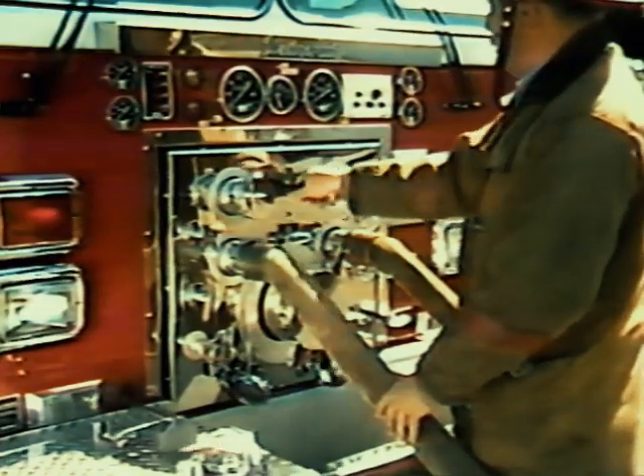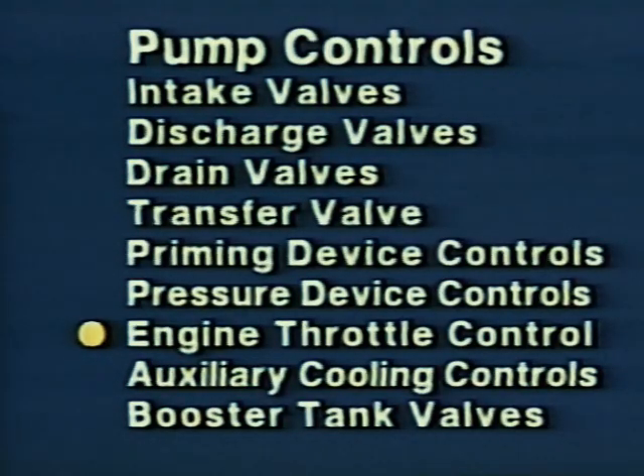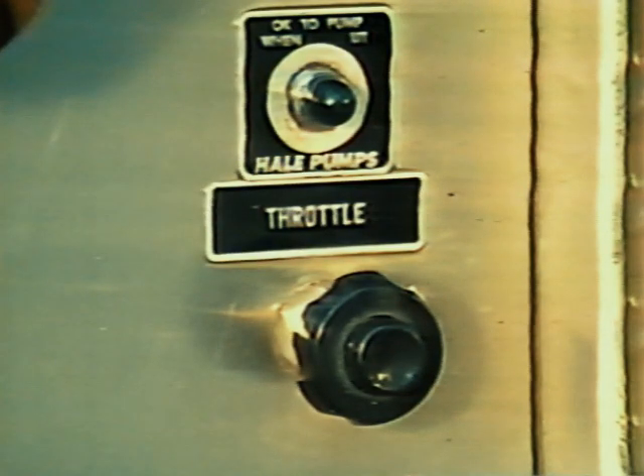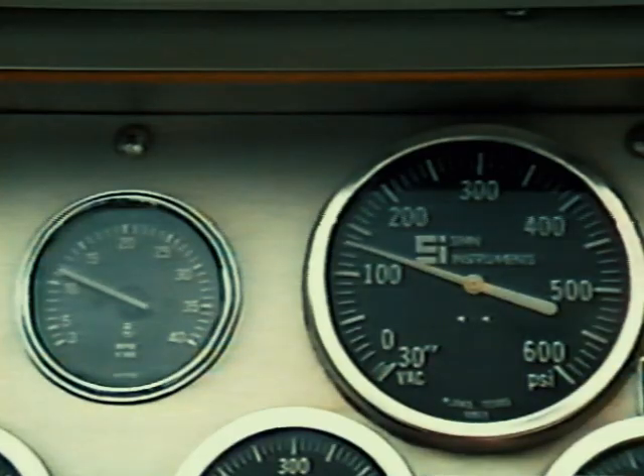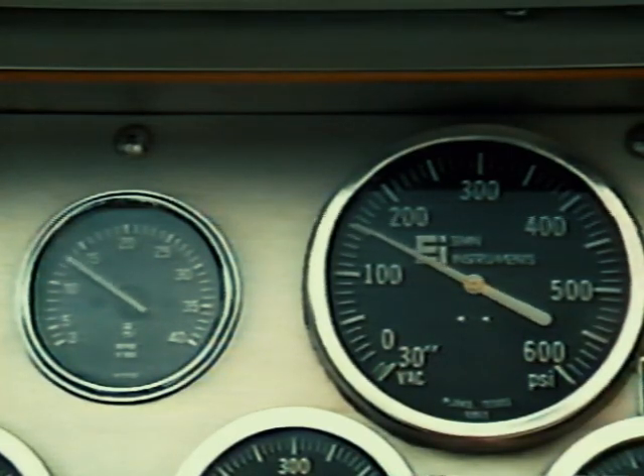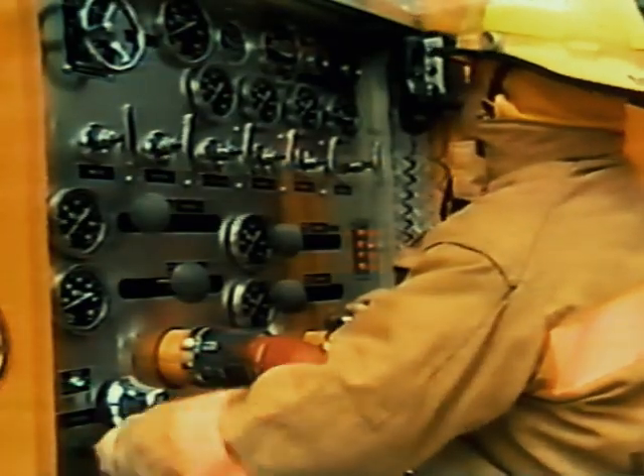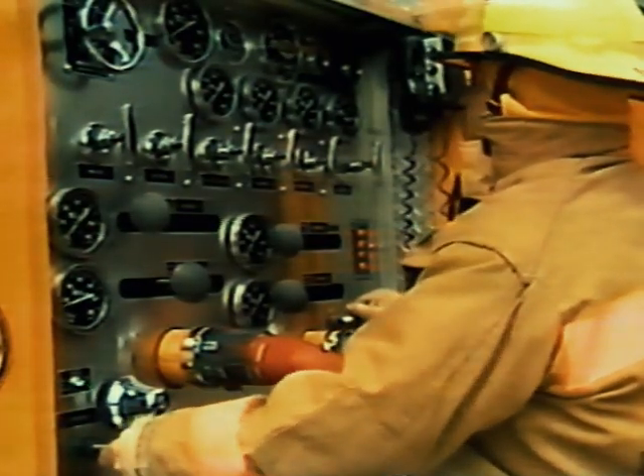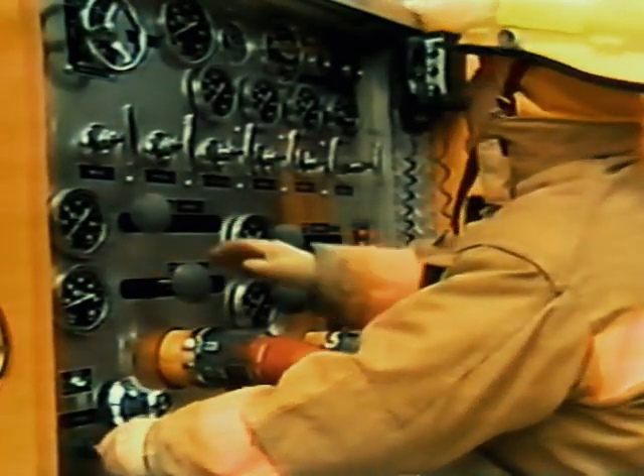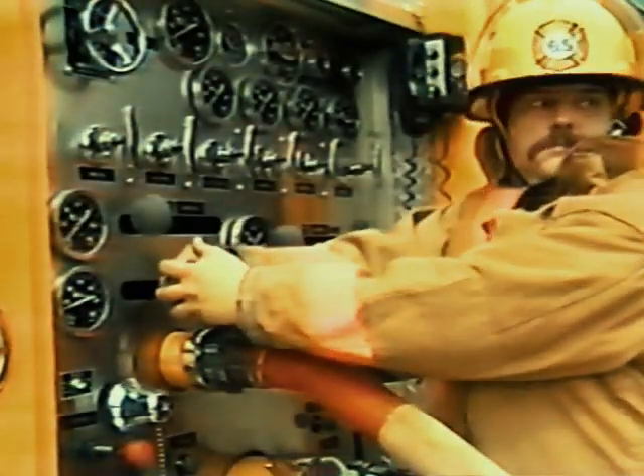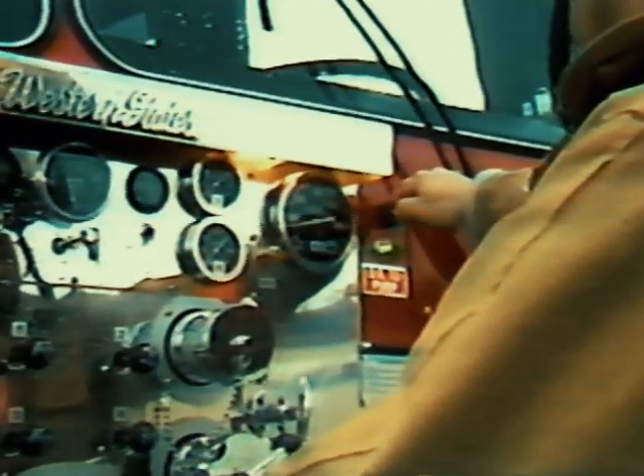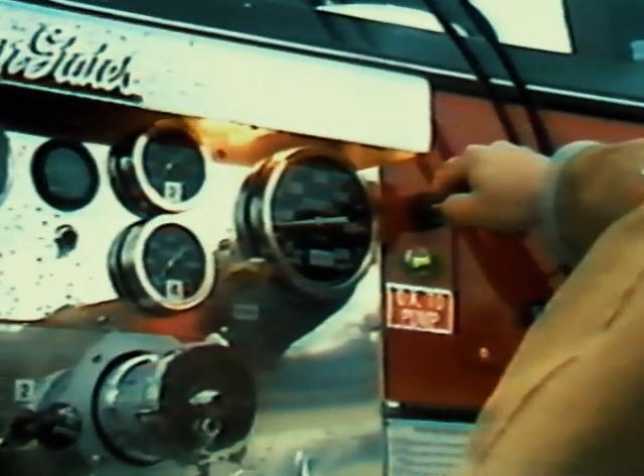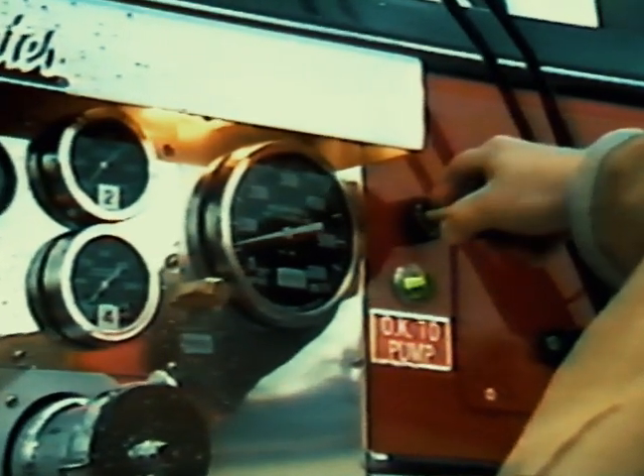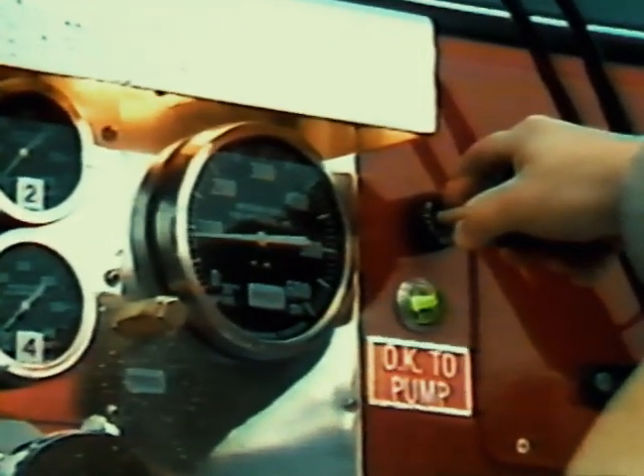The throttle control is a remote throttle that allows the speed of the engine to be controlled at the pump panel. The speed of the engine determines the speed of the pump. Adjusting the throttle control allows you to increase or decrease the flow of water to the hose lines. During operation, watch the discharge gauge and adjust the throttle to maintain the specific water flow required by the conditions at the fireground.